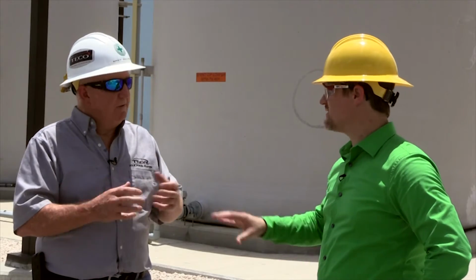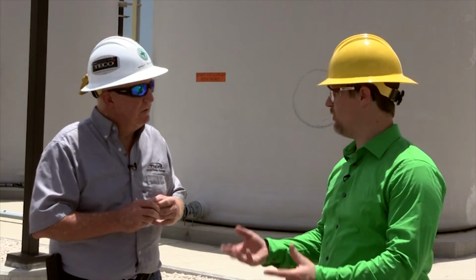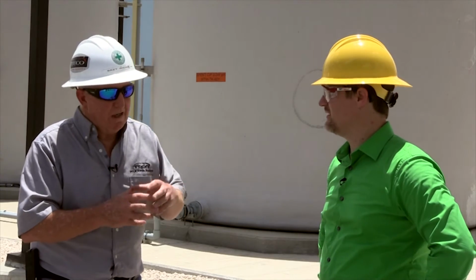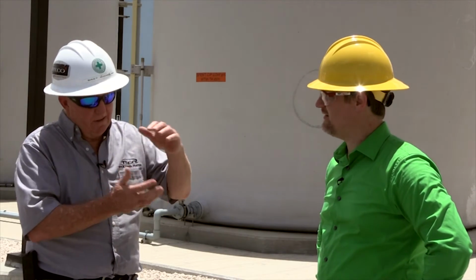We drilled two 8,000-foot deep wells here on site. There's an injection zone between 4,300 and 8,000 feet where we inject that concentrate. That's way deeper than where our drinking water comes from. Oh, absolutely, the aquifer is much closer to the surface. Between that 4,300 foot level, we have about 1,200 feet above that of very solid containment, so it's a very secure place to put our concentrate.